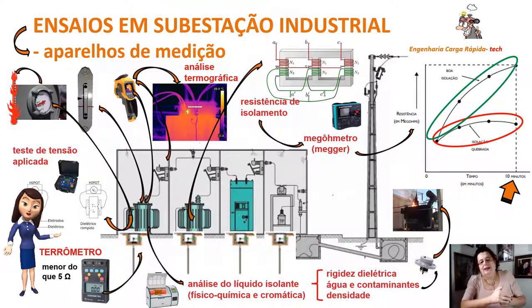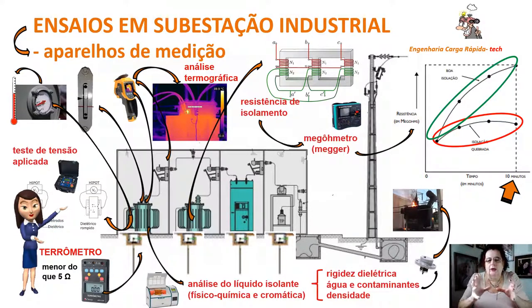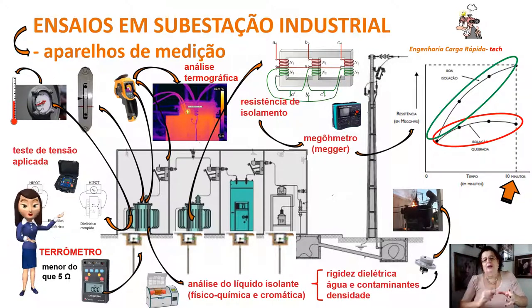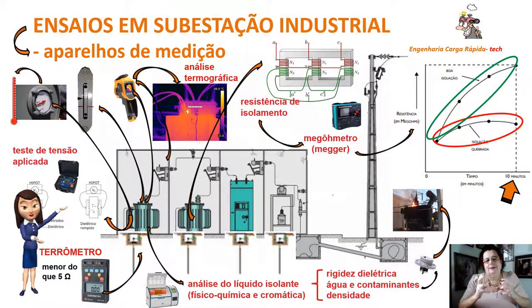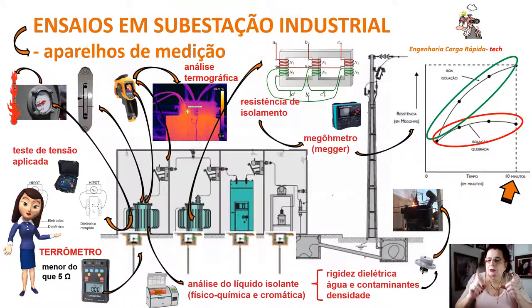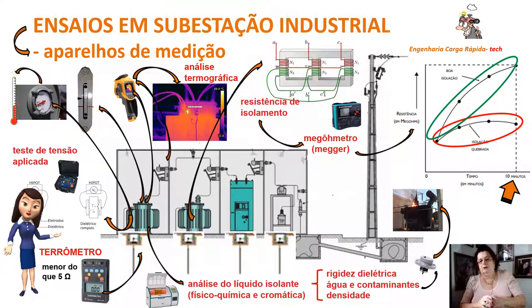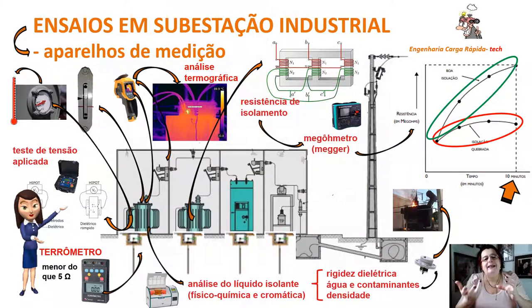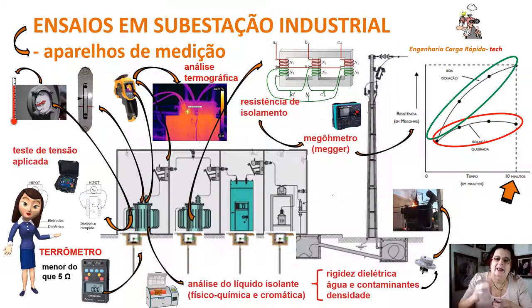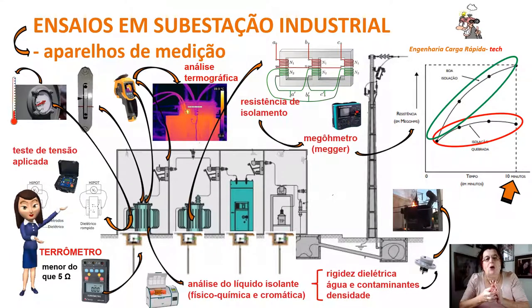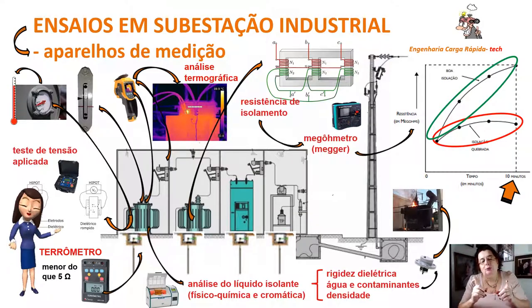Todo transformador a óleo possui uma válvula de segurança que abre quando a pressão interna atinge valores muito elevados. Transformadores de subestação podem explodir e matar pessoas dentro da subestação. Por isso, ao fazer a análise do líquido isolante, é importante verificar a válvula de alívio de pressão, garantindo que ela não esteja colada — pois se o assento colar e não abrir na pressão desejada, pode gerar explosão ou incêndio.